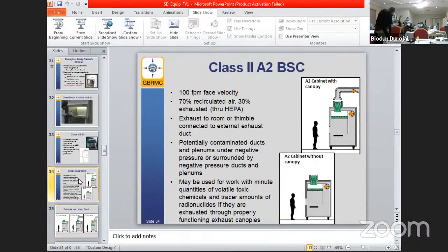And even when you're working with an equipment, there are signals. So for those who say they work with a biosafety cabinet, there are signals that will tell you to invite the professional. There are indicator lights. Some of them, if the green light is not there, it tells them that something is wrong. If the red light shows, so these are indicators. You can use them to check the efficiency of the specific equipment.